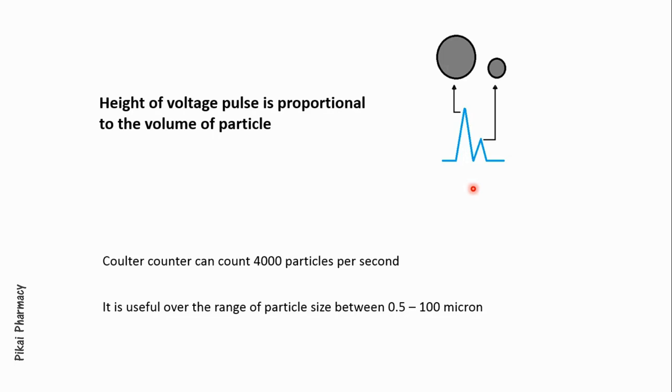The Coulter counter can count 4000 particles per second, and it is useful over the range of particle size between 0.5 micron to 100 micron.